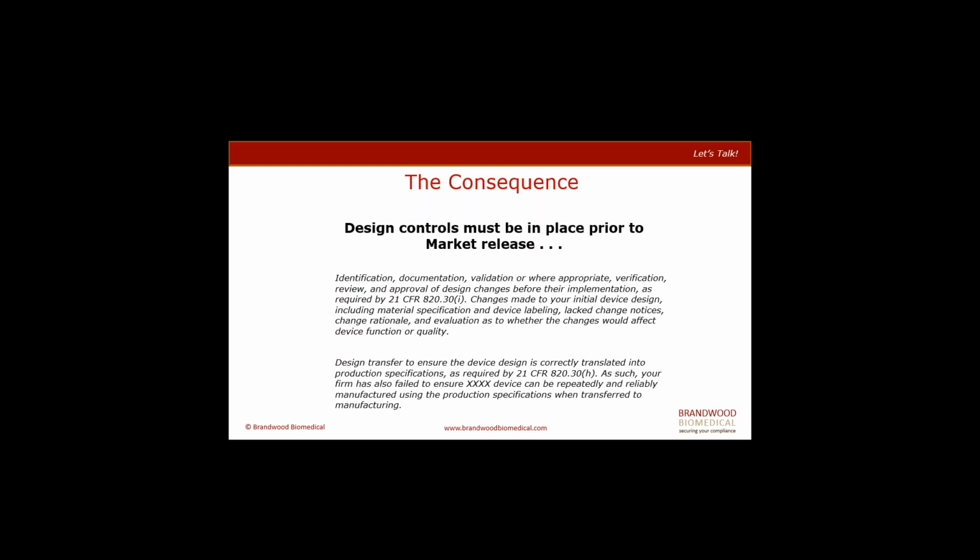So, the consequence of not undertaking appropriate design controls and not having the appropriate procedures in place. I've taken a couple of paragraphs from a warning letter to an unfortunate manufacturer. It basically identifies that there's a lack of procedures and records, so there was no evidence of particular activities being undertaken.